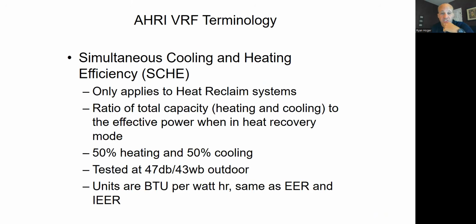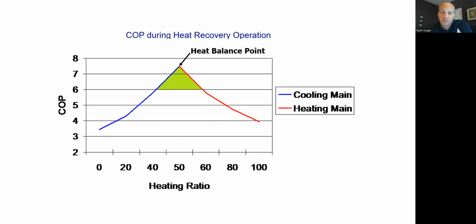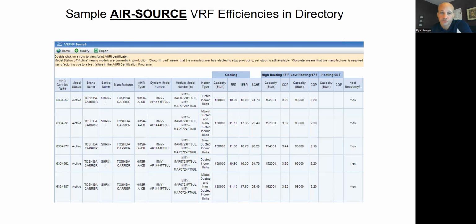Then you get a 5th one because it's VRF in this case, and that is simultaneous heating and cooling. So what this does is it says, hey, if we just operate the heating and cooling equally right now, pretend we have this moment in time where everything's operating the same exact quantities, how efficient will we be then, right? So we have that rating. It's in terms of EER, right? But it's going to be a giant number because nothing's getting rejected outside. So it's going to be way up here, right? How efficient am I in heating? How efficient am I in cooling? As those things track together, it's like I'm shoving heat from one zone to the other. How efficient am I in the middle? And all those rating systems are in here.